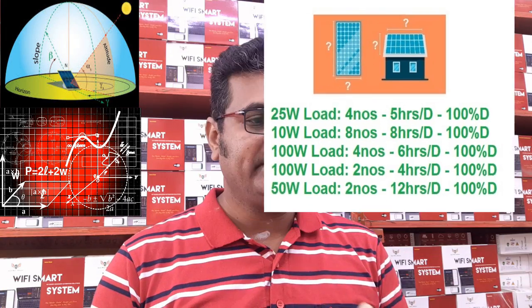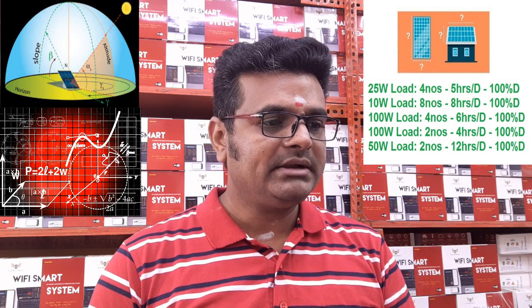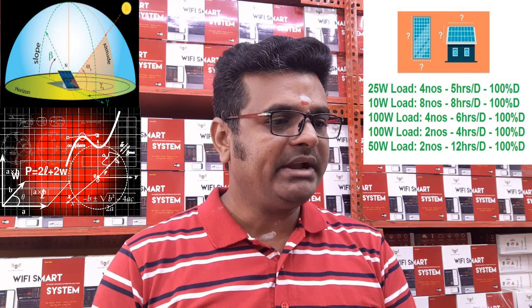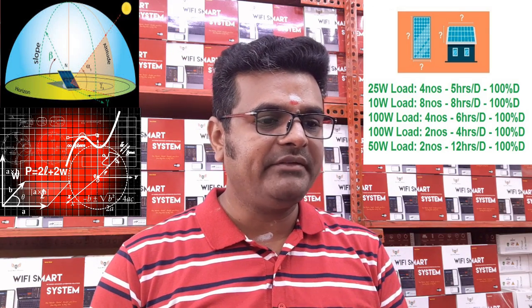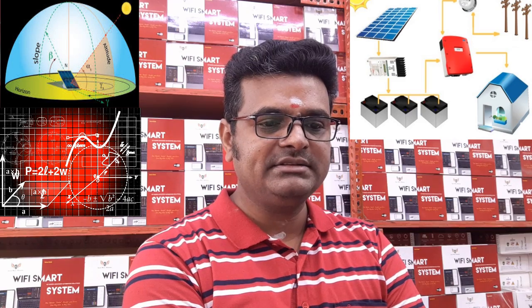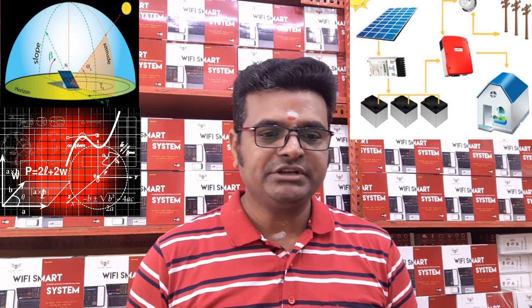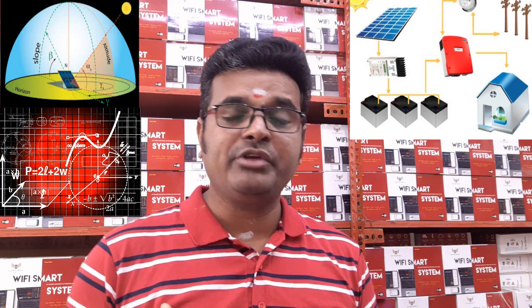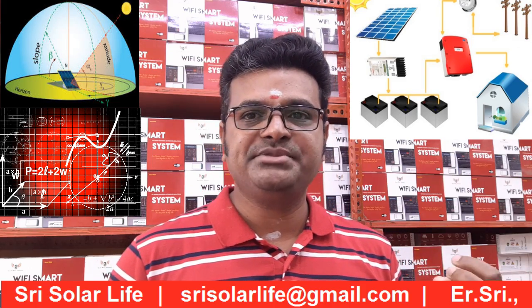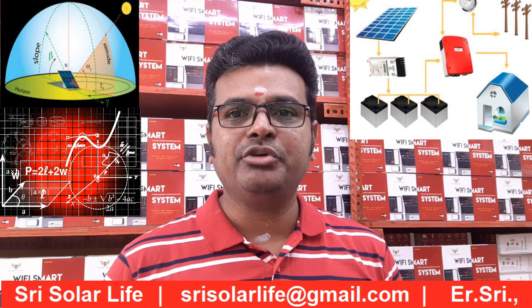Here are the load calculations we have considered: 25 watts, 4 numbers, running 5 hours per day; 10 watts loads, 8 numbers, running 8 hours per day; 100 watts loads, 4 numbers, running 6 hours per day; 100 watts loads, 2 numbers, running 4 hours per day; 50 watts loads, 2 numbers, running 12 hours per day. All loads are calculated based on 100% duty cycles. According to these calculations, you need almost 2022 units per year — that is the total power consumption for this load if running for the entire year.